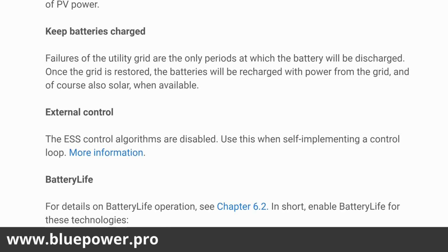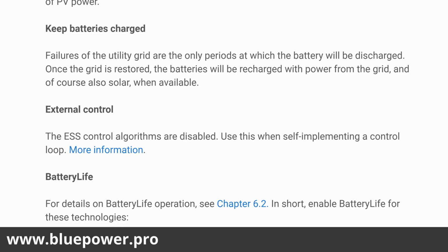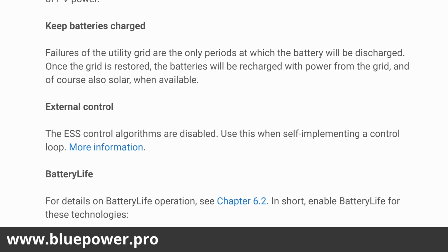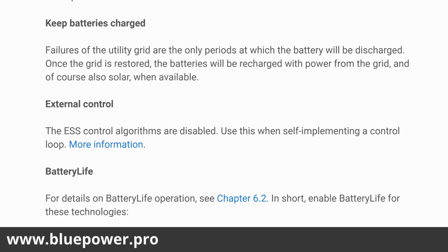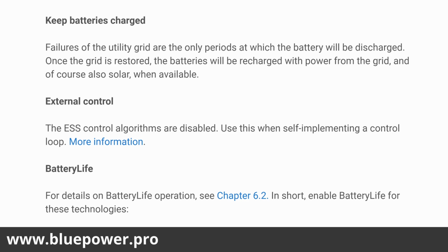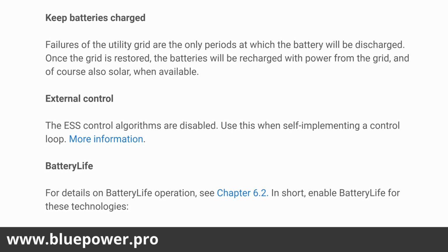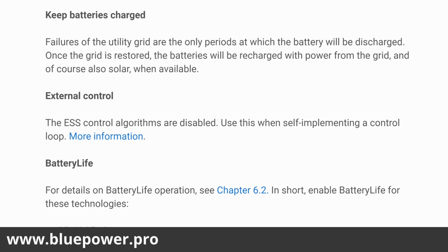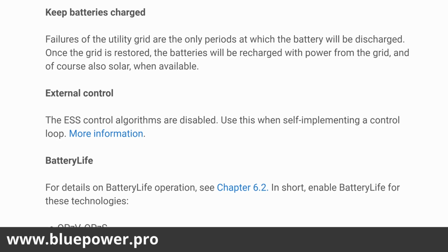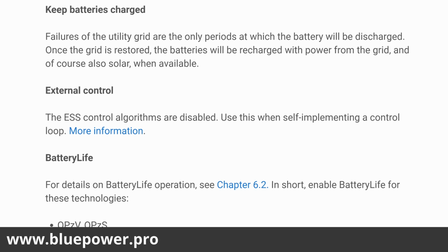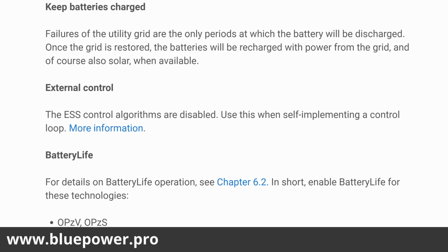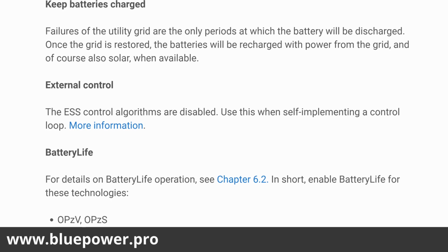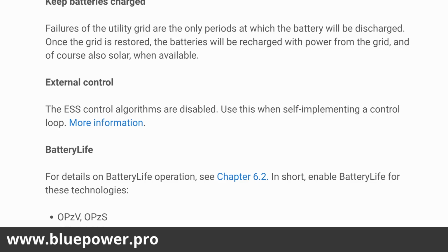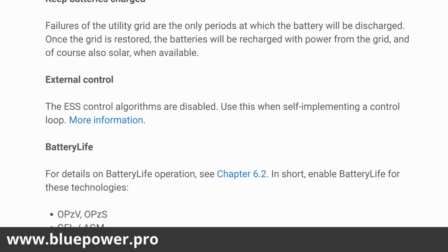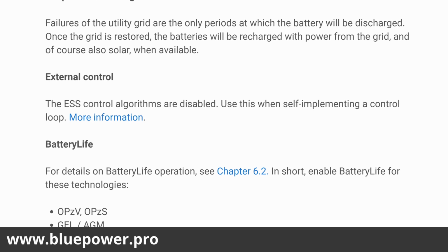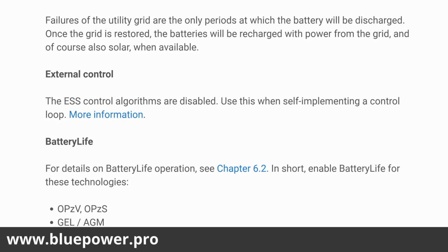Optimized without battery life will only give you one value that you can set, and that value will always be the level to which the battery gets discharged. Irrespective of whether you had 1 kilowatt hour of excess PV for the day, your battery will only charge that extra 10% for the day and use that 10% again at night. So it's not optimal for lithium batteries. Lithium batteries do require balancing at least once a week or once every 2 weeks. So the optimized without battery life algorithm is not recommended.